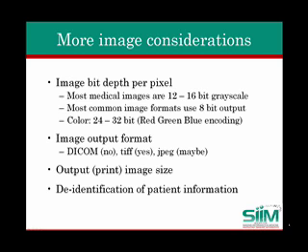There remain a few more details regarding other characteristics of the image itself. First, the bit depth per pixel determines the number of shades of gray, or color, that can be rendered by the display. Most medical images have a bit depth of 12 to 16 bits. An image with 12 bits has 4,096 unique gray levels, providing differentiation of local details according to window width and window level adjustments. Most common image formats have 8 bits, with 256 unique gray levels. Proper grayscale rendition during conversion from 12 to 8 bits by setting window width and window levels prior to converting images from a PACS is crucial, as there are limited capabilities afterwards.